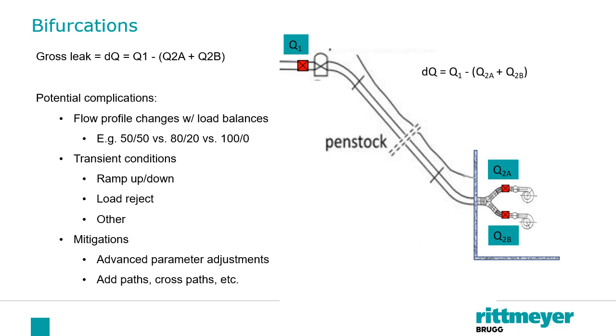Turning back to this bifurcation example, if we choose to do penetrating transducers after the bifurcation, then we simply have to sum those 2 flows together to get the lower flow meter, and it works into the equation just like that. However, there are some interesting challenges that come up. If it's calibrated with both units running, then what happens if only one unit is running? Does the flow distribution profile through this flow meter change? And it can. And if so, what effect does that have on the flow reading and on the balancing of the whole PLDS system?